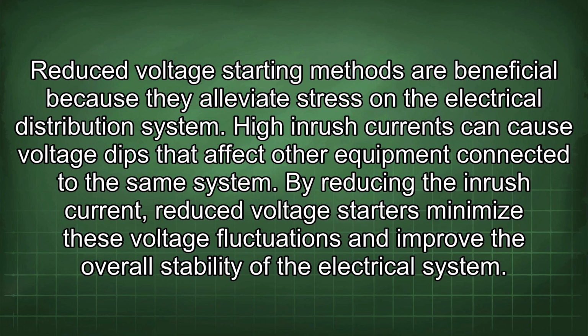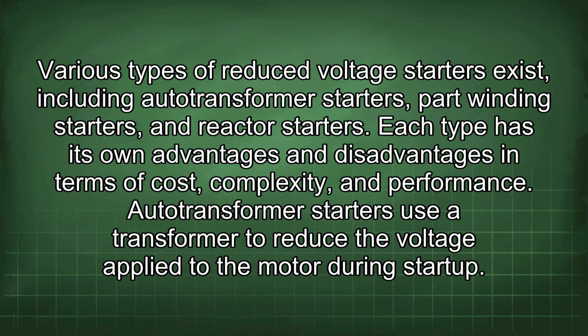Reduced voltage starting methods are beneficial because they alleviate stress on the electrical distribution system. High inrush currents can cause voltage dips that affect other equipment connected to the same system. By reducing the inrush current, reduced voltage starters minimize these voltage fluctuations and improve the overall stability of the electrical system. Various types of reduced voltage starters exist, including auto-transformer starters, part-winding starters, and reactor starters. Each type has its own advantages and disadvantages in terms of cost, complexity, and performance.